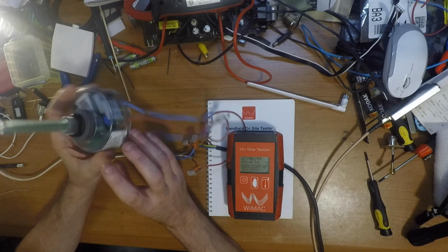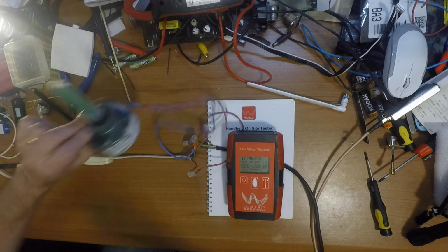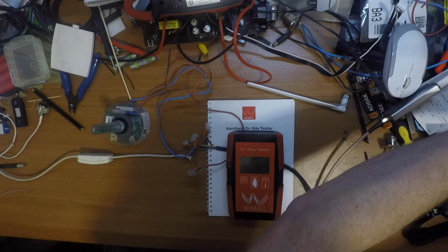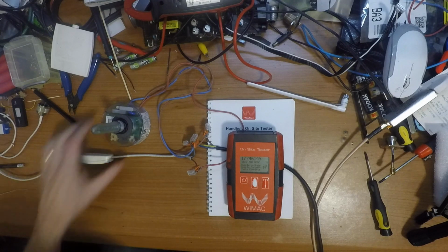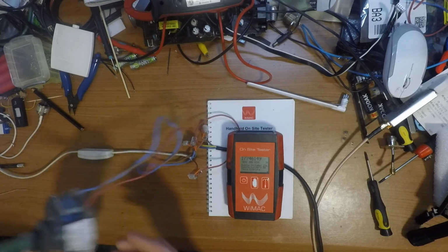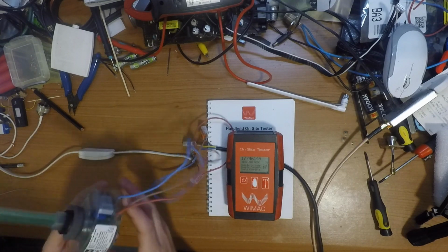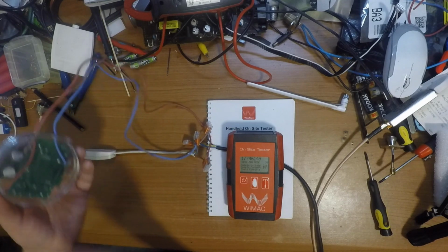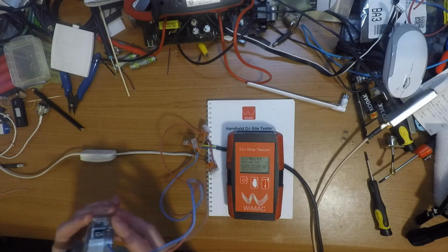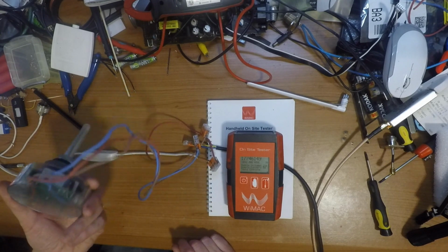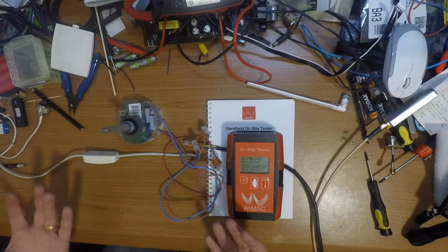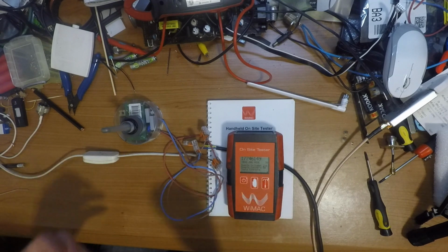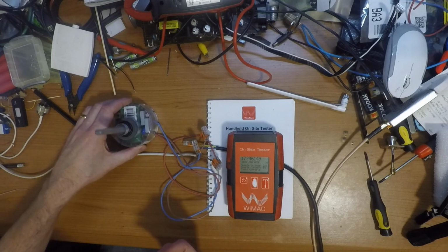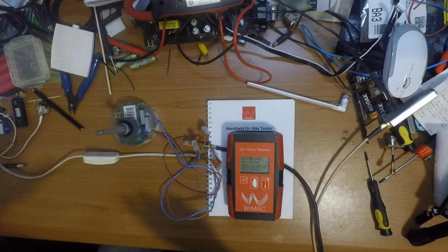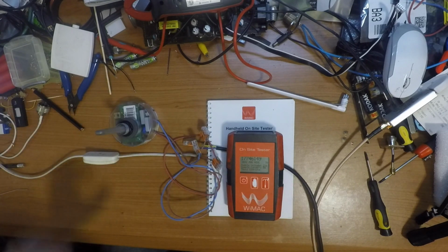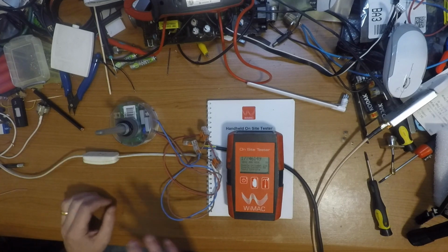There are actually a few versions of these devices here from Harvard Electronics. Before I touch it and get a zing, I will just turn the power off, because that would be ruinous to my day. There's a few versions. This is the really basic version, which just turns lights on, off, and gives you a power reading. There's another version of this, which looks almost identical. It has another socket on, and that extra socket is for what they call in the industry a presence detector. Not Santa Claus presence, but the presence of people. That could be something like the little passive infrared movement sensors you get in alarm systems. And the idea is that rather than having street lights that are controlled centrally, and they all turn off and turn on at whatever time you set them up, you can set the lamps with these presence detectors to only turn on when somebody's there.